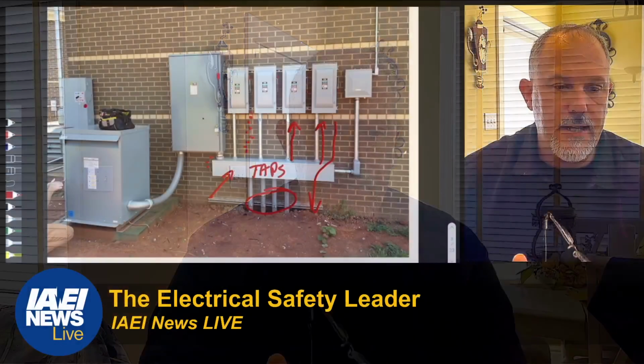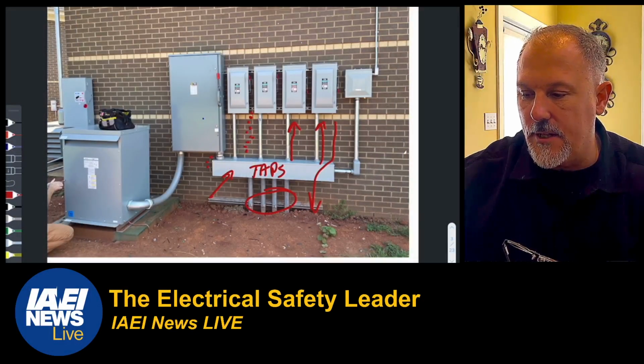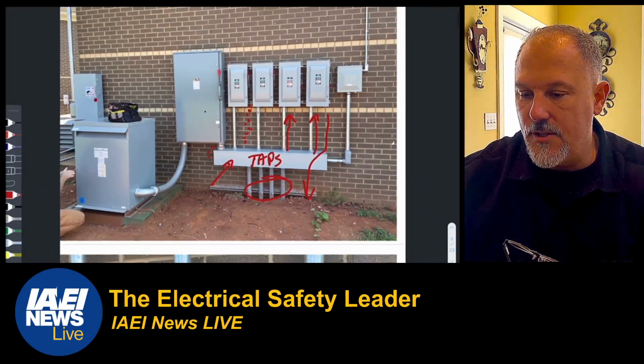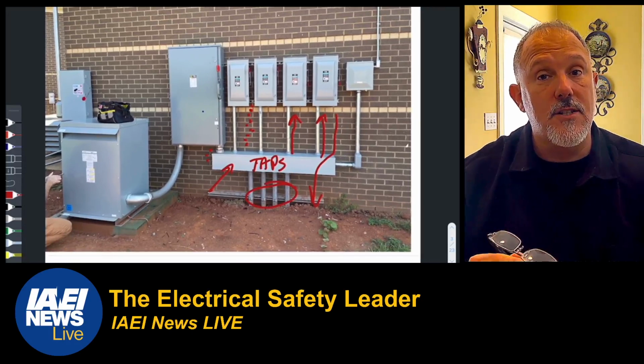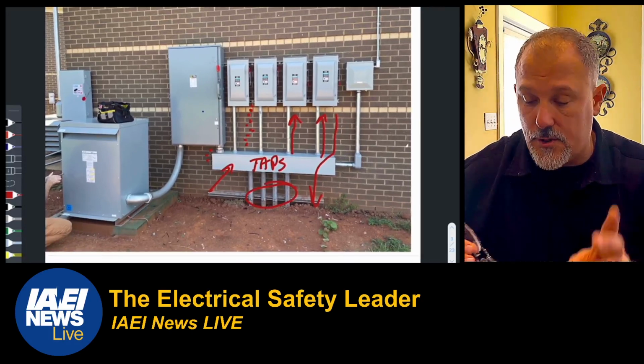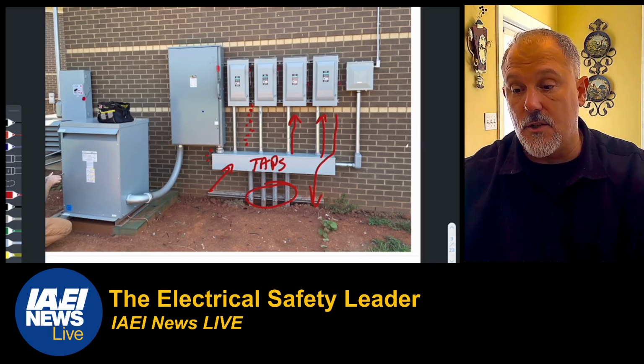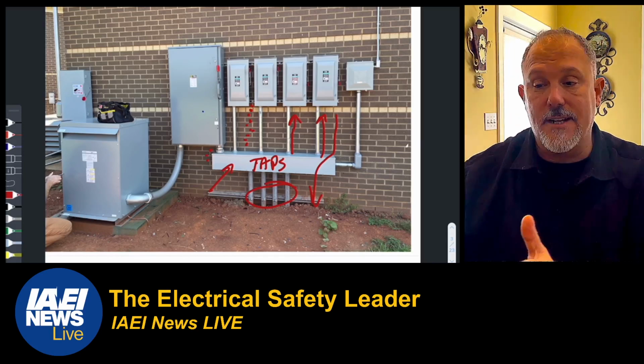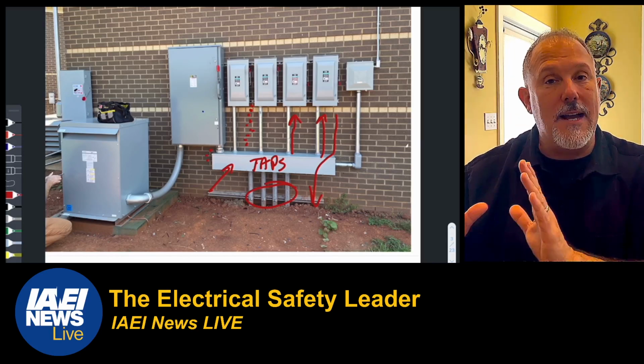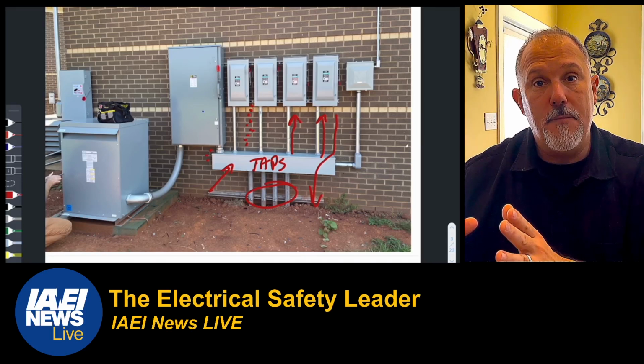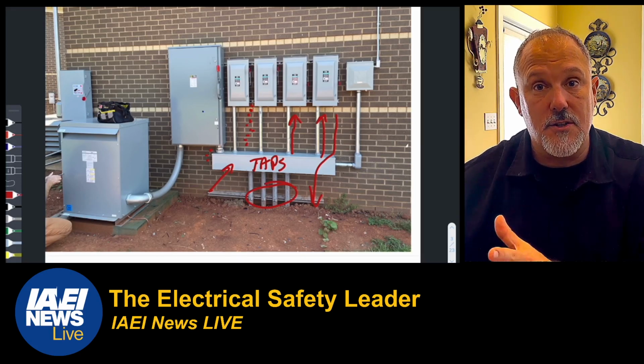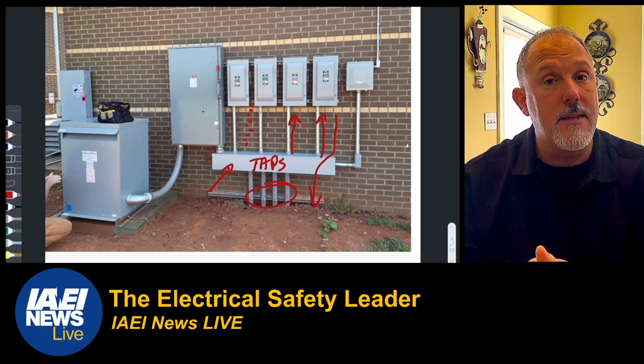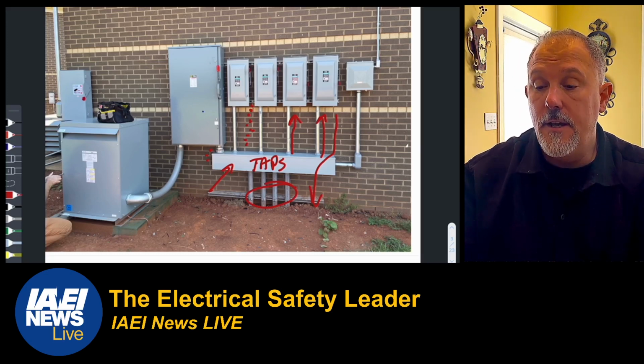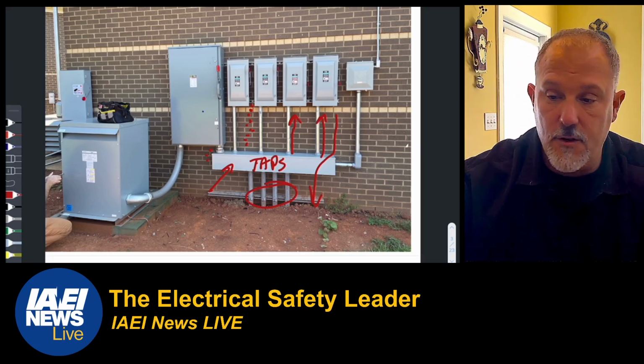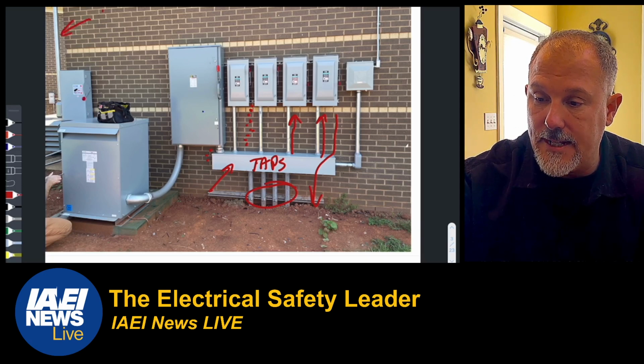If you remember, this was the application that we were dealing with. You'll notice that this is not service equipment. There are a couple of unique things about this application. One is it looks like a service. It looks like what you might see on the outside of a building that would be treated as a service because the utility would be connecting, but this is not a service. Over here on the left-hand side, that's a feeder.